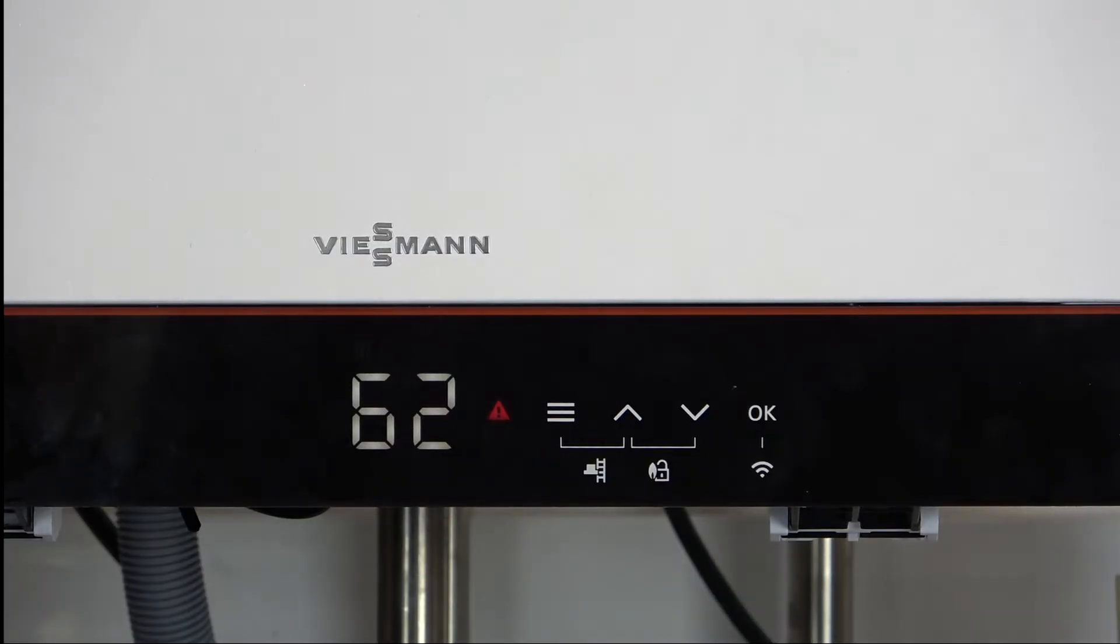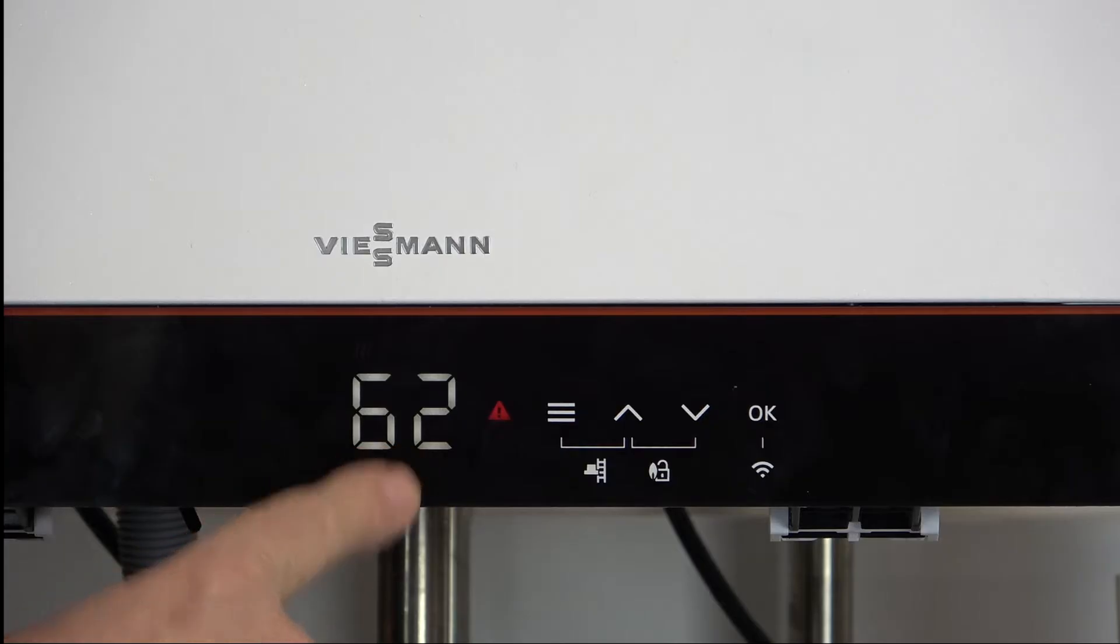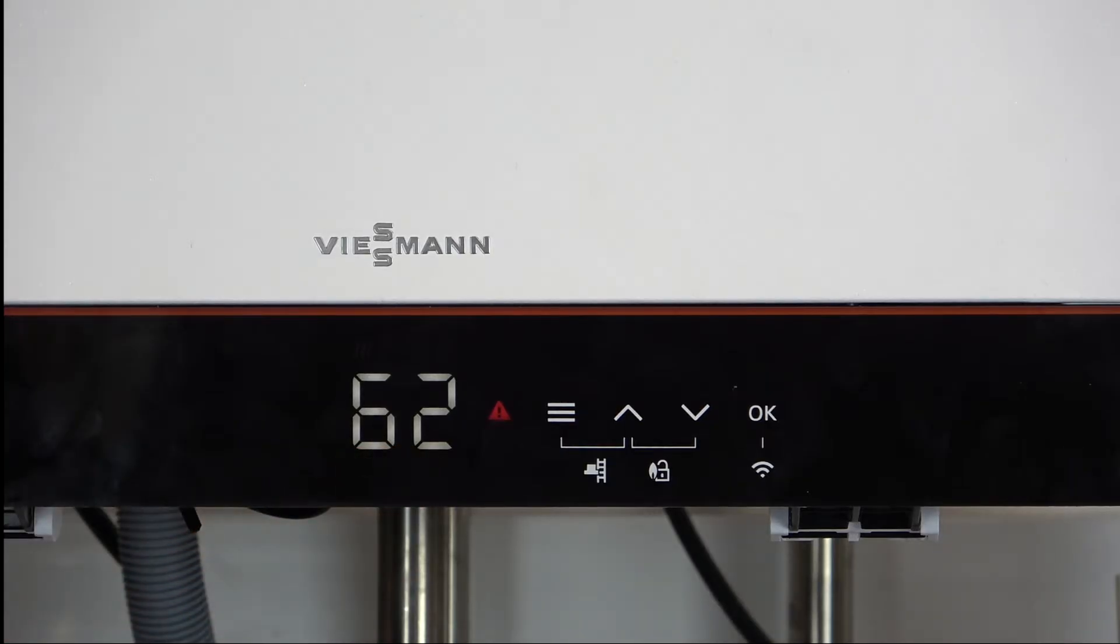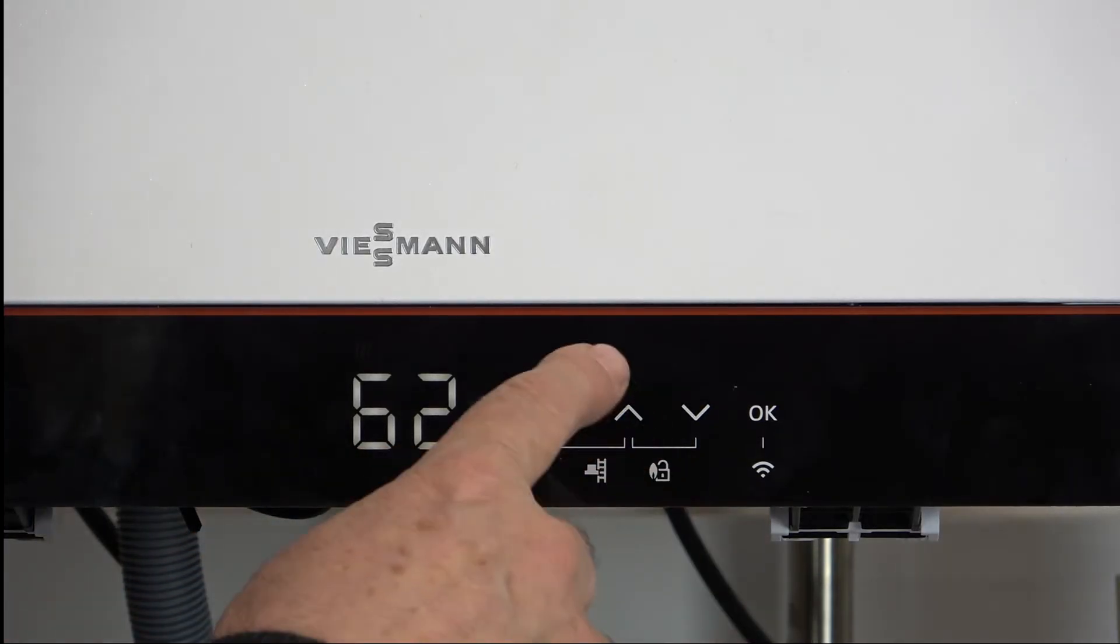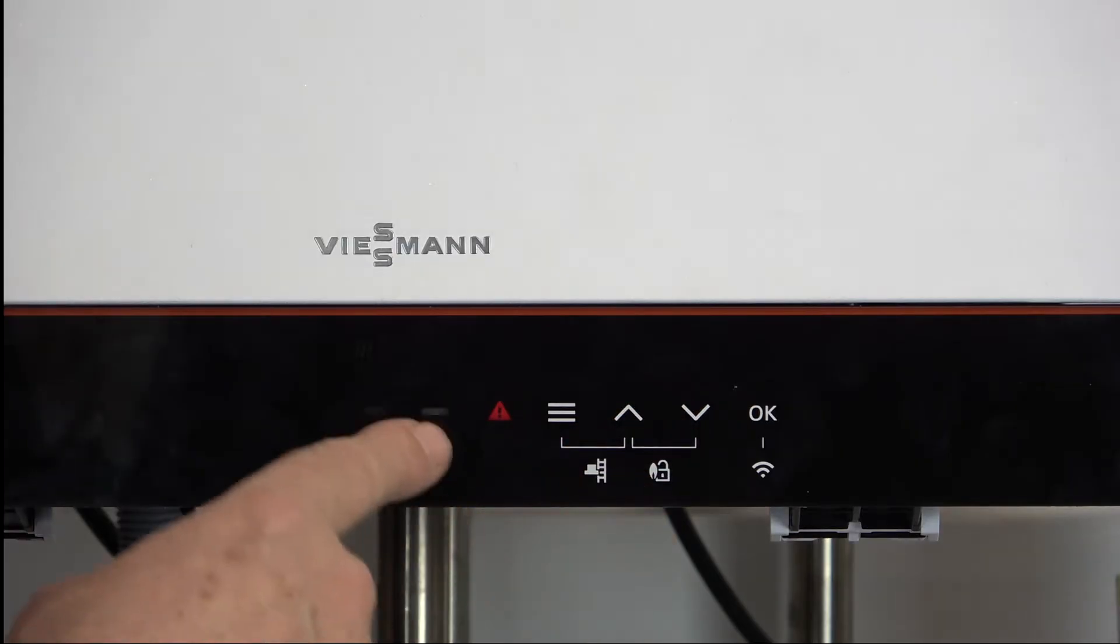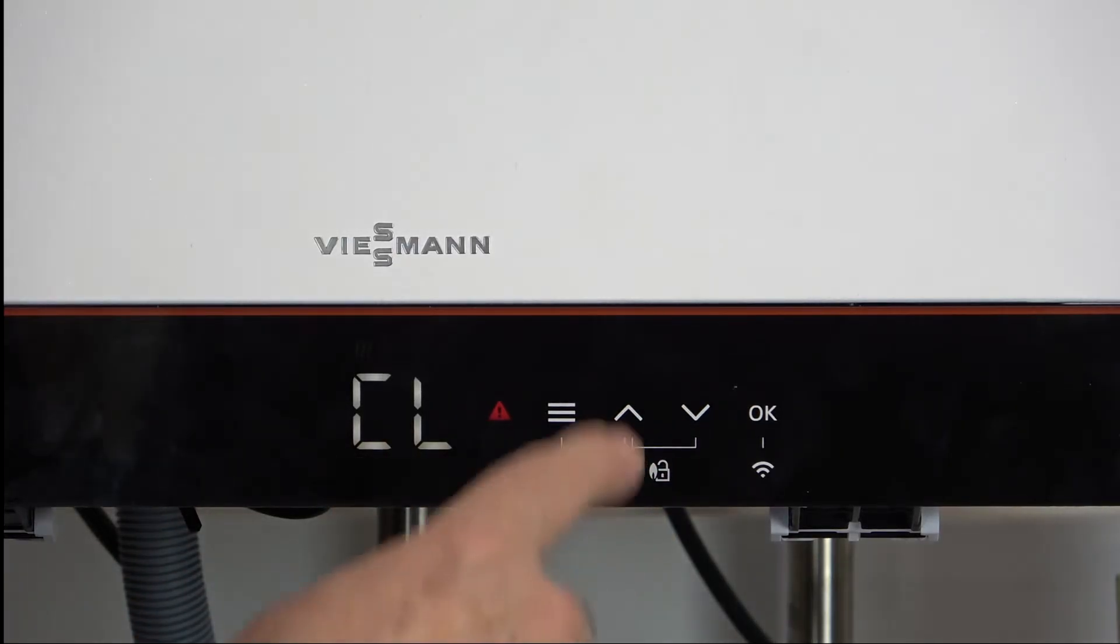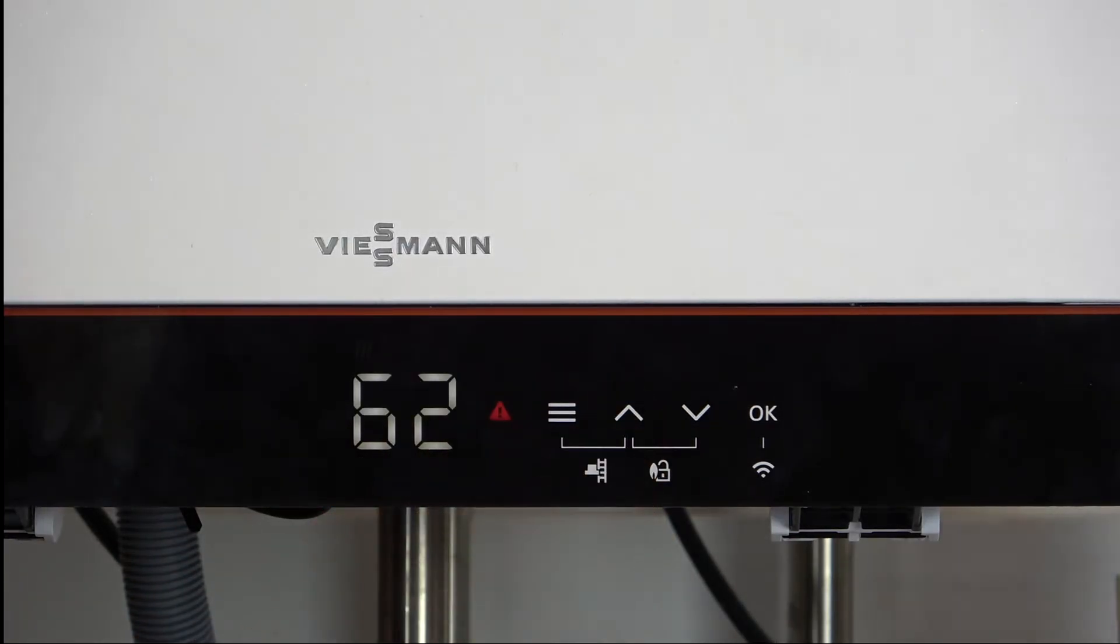Now one of the issues with resetting the boiler is that you can't reset it if the number 62 is displayed. The only way you can reset the boiler is if we've got CL. So you can see what we've done, I'll just do that again.